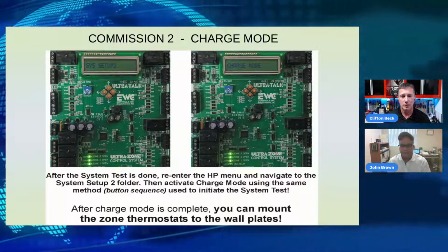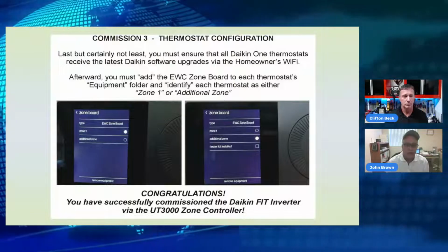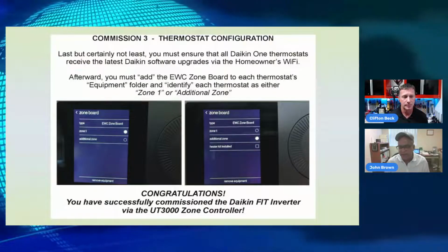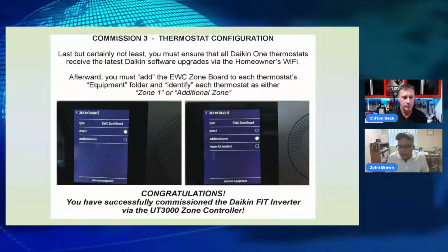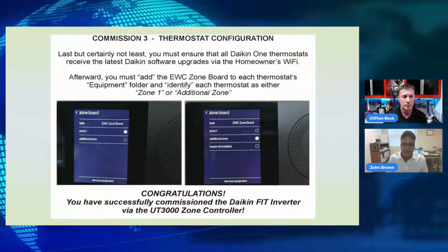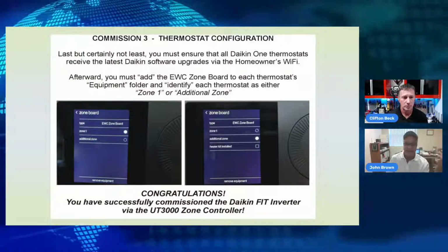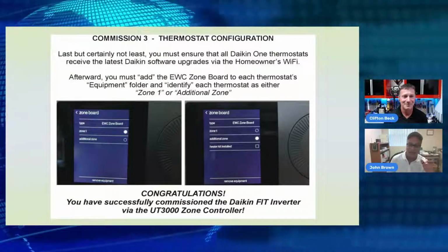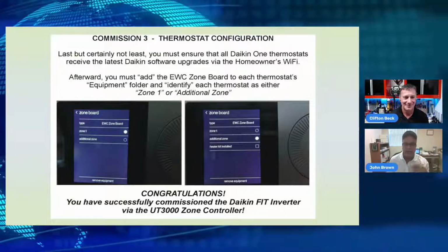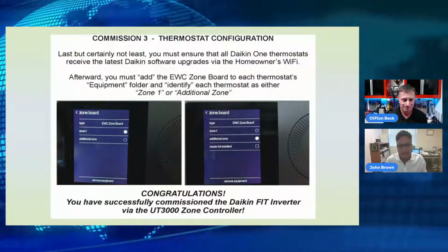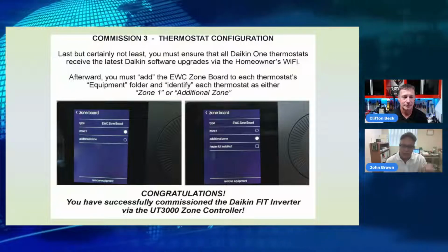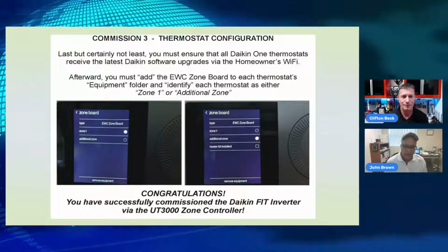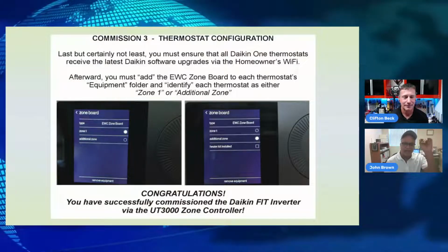Okay. So we're in charge mode. And remember, charge mode is an hour, and it may not take you an hour. You don't have to wait the entire hour. If you finished, your subcooling is good, the very cool inverter told you your subcooling is good, you trimmed your charge a little bit, you finished in 20 minutes, 30 minutes, simply use the buttons, go back into the system setup folder, go back into the charge mode and turn it off.